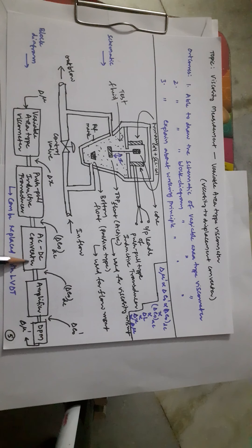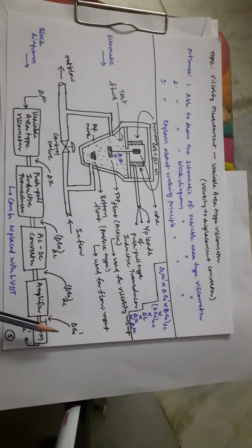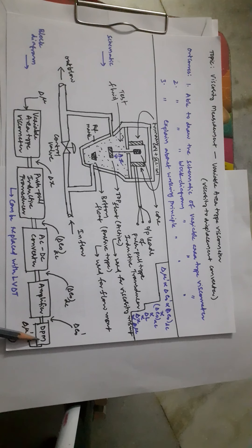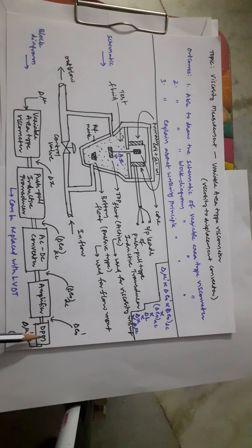The AC output voltage from the push-pull or LVDT transducer must be converted to DC using an AC-to-DC converter or phase-sensitive demodulator. This stable DC voltage is then amplified using an amplifier to give an output delta E₀', which is displayed on a digital panel meter. The panel meter displays voltage values calibrated in terms of viscosity, represented as delta mu dash.